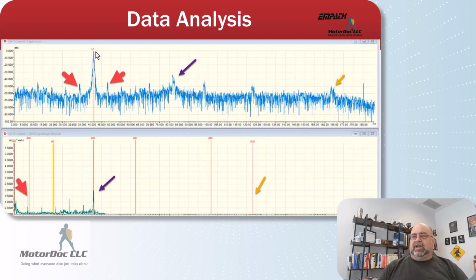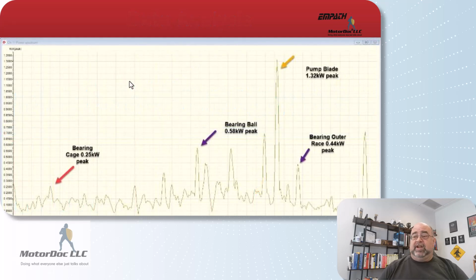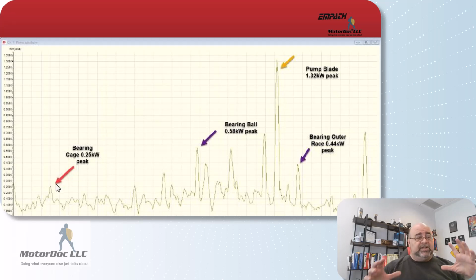So in any case, count down to the level that tells you the condition. Okay, these are all above 65 dB down, but I have a high noise floor, so I'm looking at above the noise floor. It's still 10 dB above the noise floor, meaning I have an issue. So when I come over here and take a look, I can convert all of this over to watts or kilowatts. So 250 watts for a cage, because it's a larger bearing. You normally won't see anything more than a kilowatt in a standard bearing unless it's under a lot of stress. What we're actually reading is the friction losses.